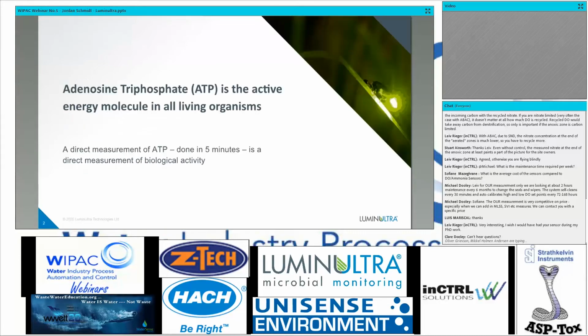So what is ATP, or adenosine triphosphate? It's the active energy molecule in all living organisms. A direct measurement of ATP, which can be done in approximately 5 minutes, is a direct measurement of all biological activity. And the reaction that we're actually measuring is the same reaction that occurs in the tail of a firefly. So that's an ATP reaction. It's generating light. Similarly, we can harness that and measure the light output to measure quantity.